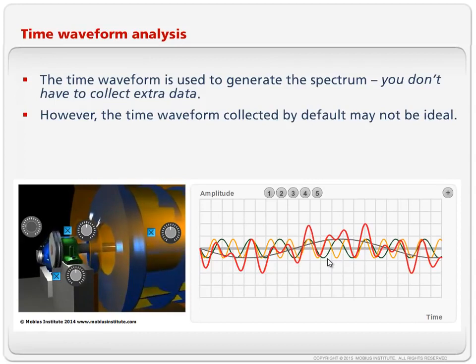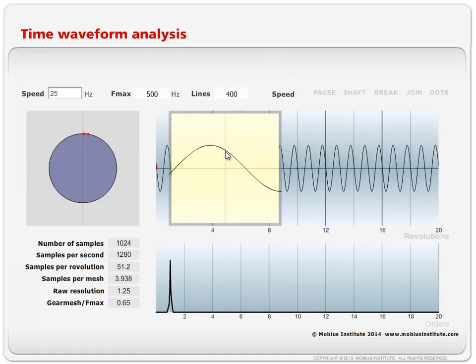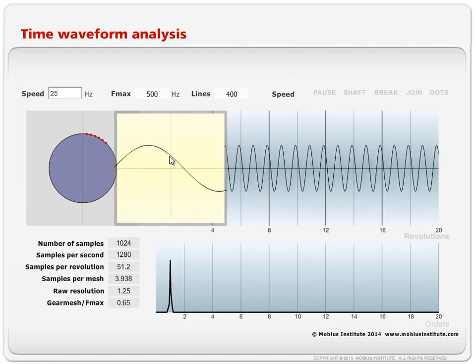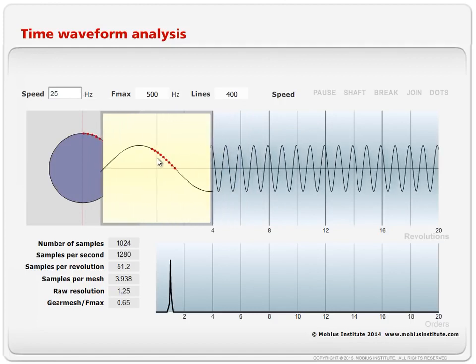And that's where a lot of vibration analysts get caught up. They look at the time waveform and they see it just looks boring. It just looks like a whole lot of just blue graph, and they say, it's not telling me anything, I'm not going to bother with this anymore. Please bother. Please just make sure you get the settings right. We spend a lot of time on this in training to make sure people understand why. And what I'm about to show you is a simplified explanation of why people get it wrong and what you need to know.